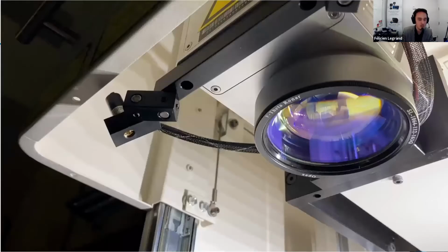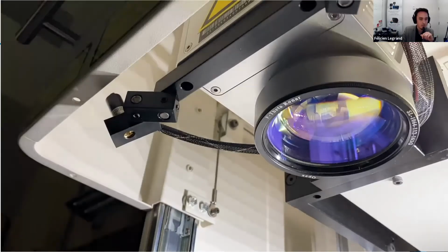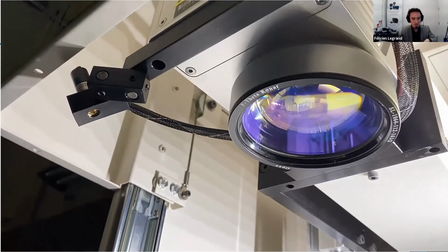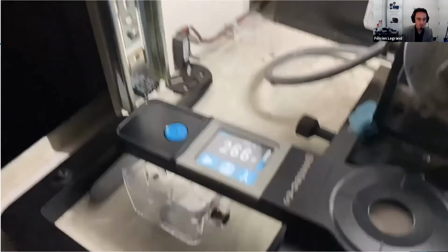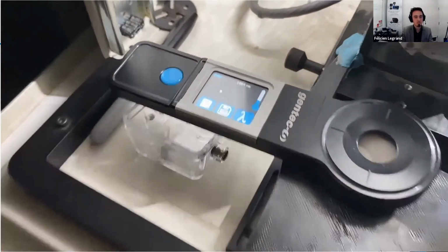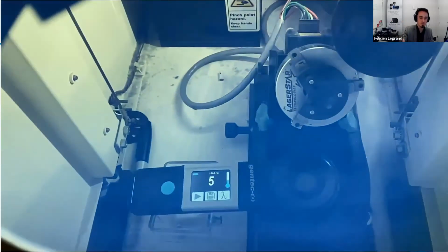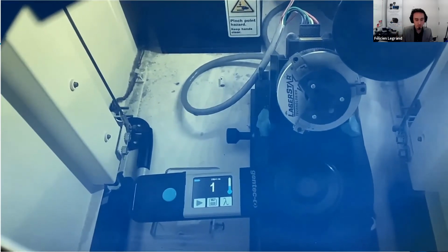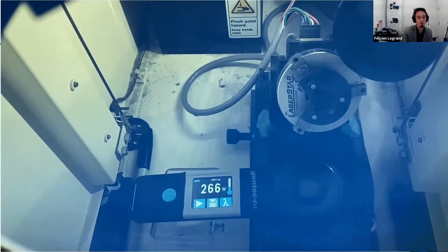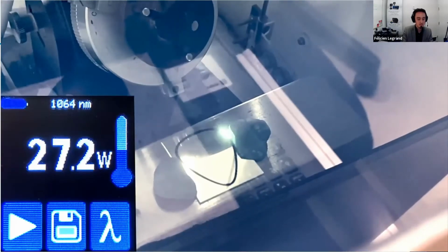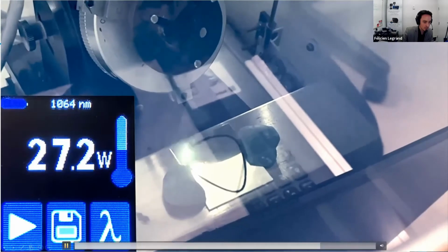So then, a quick video here. That's the output of a welder system that is used for welding metals, facing downwards to a power meter there, which is a Pronto 250. Just pressing play, and the detector will wait for a beam to heat up the surface of the detector. Once that is done, it's counting 5, 4, 3, 2, 1, 0, and displaying the average power of this laser, about 26, 27 watts continuous. So here, I'm going to stop the video quickly.